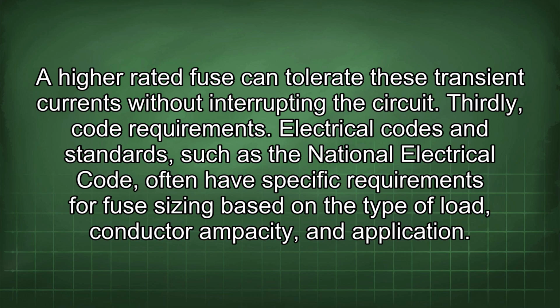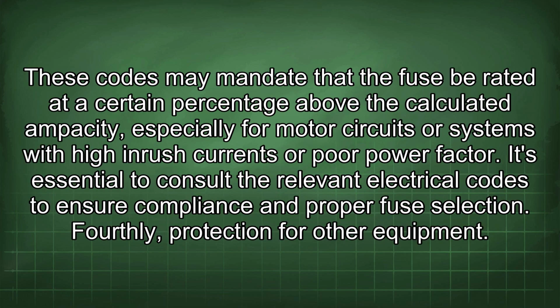Thirdly, code requirements. Electrical codes and standards, such as the National Electrical Code, often have specific requirements for fuse sizing based on the type of load, conductor ampacity, and application. These codes may mandate that the fuse be rated at a certain percentage above the calculated ampacity, especially for motor circuits or systems with high inrush current or poor power factor. It's essential to consult the relevant electrical codes to ensure compliance and proper fuse selection.